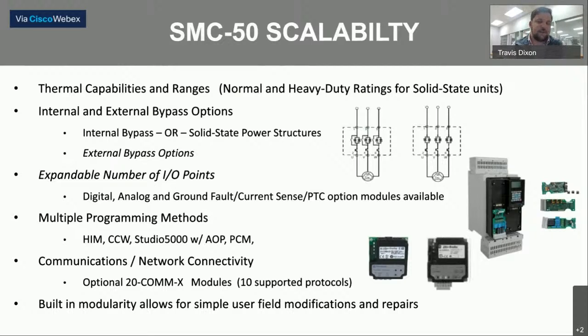So SMC 50 scalability, that's one of the many strengths of both the internal bypass and solid state SMC 50. Some of the scalability examples: normal and heavy duty thermal ratings. You can select if you want an internal bypass, which is really focused more around standard applications, fans, pumps, conveyors, heat sensitive applications, or a solid state structure, which is really for demanding applications like crushers, shredders, shock loads, a high duty cycle. It's a lot more rated for dirt and debris. You can also use an external bypass with the solid state version, if you prefer that.